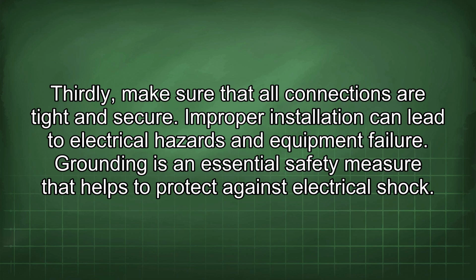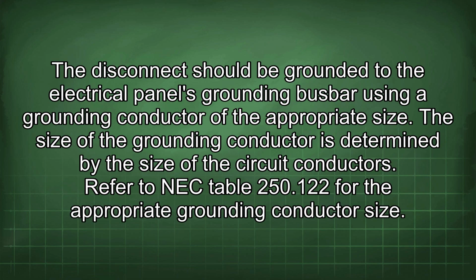Grounding is an essential safety measure that helps to protect against electrical shock. The disconnect should be grounded to the electrical panel's grounding busbar using a grounding conductor of the appropriate size. The size of the grounding conductor is determined by the size of the circuit conductors. Refer to NEC Table 250.122 for the appropriate grounding conductor size.